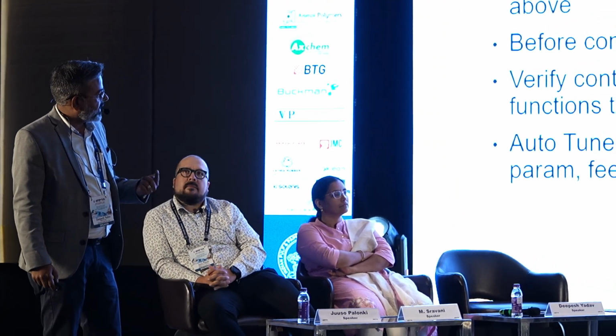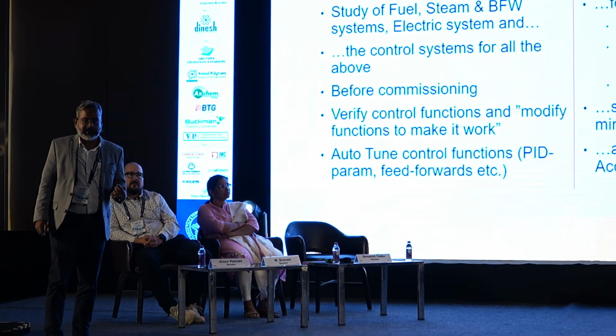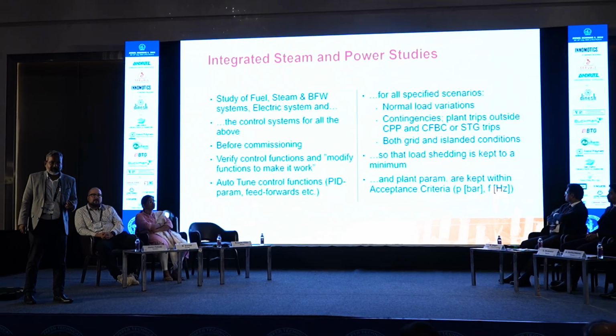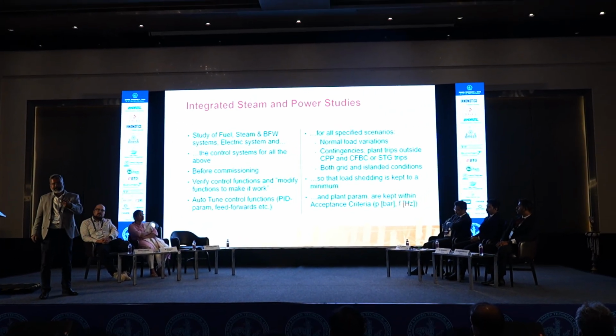We studied their fuel systems, steam systems, boiler feed water systems, electrical, and basically the controllers behind the process side as well as the electrical side before commissioning, and we verified that their control functions work. We developed some new logics for them to run the plant in a complete auto mode. We tuned their PID parameters for normal as well as contingency situations, so that load shedding is kept to a minimum, so that the plant parameters are kept within acceptance criteria, especially the main steam header pressures, and the frequency in an islanded mode remains within the protection limits.